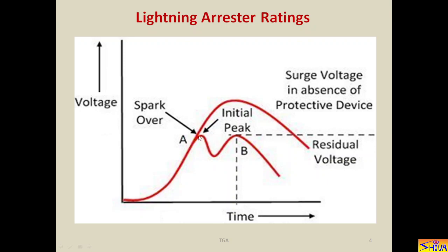So when the lightning arrestor sparks over, this voltage suddenly drops. From this point, as lightning arrestor has sparked over, the discharge current will start flowing. So discharge current is increasing. This voltage is also increasing. So the discharge current will attain its maximum value. Then it will start reducing. And this residual voltage or discharge voltage will start from here, will also attain some maximum value, and then it will start reducing. So this maximum value is called as residual voltage or discharge voltage.